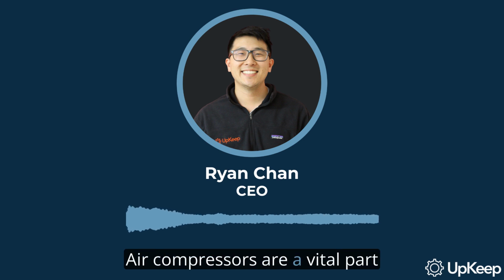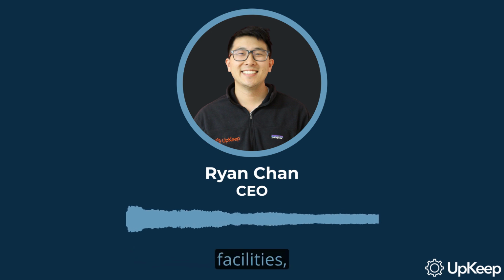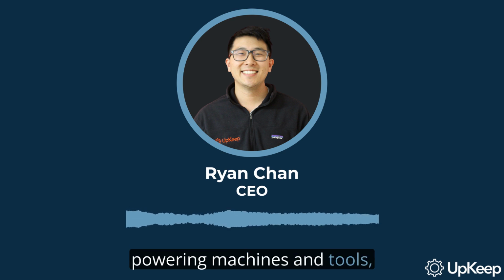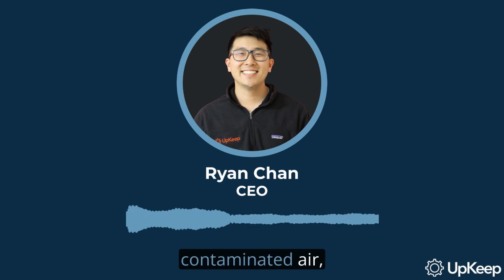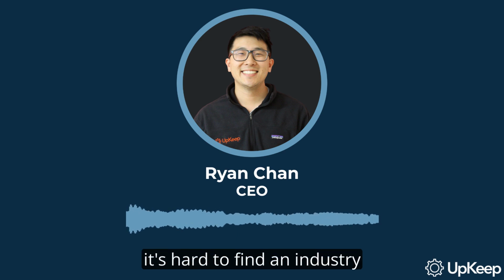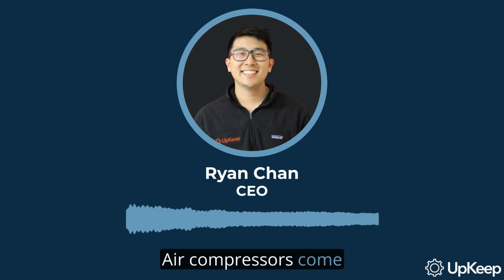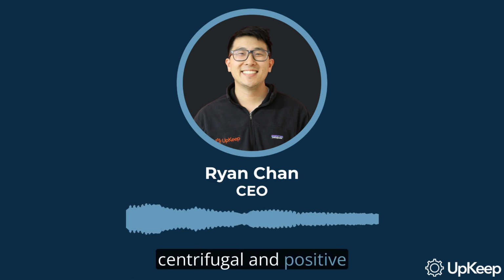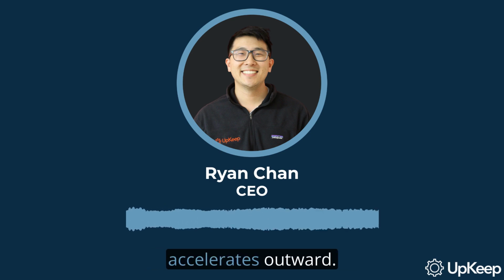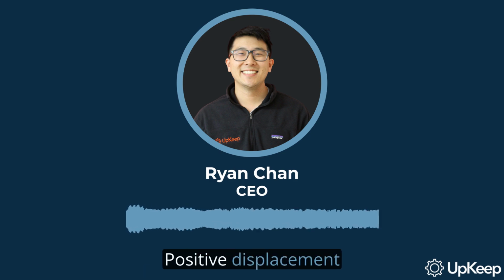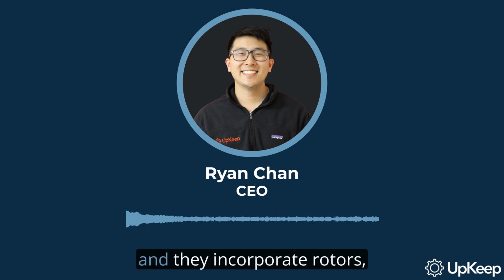Air compressors are a vital part of commercial and industrial facilities, powering machines and tools, exchanging clean air for contaminated air, and running material handling equipment. In fact, it's hard to find an industry that doesn't use air compressors in some capacity. Air compressors come in two main types, centrifugal and positive displacement. In a centrifugal compressor, gas enters the center and accelerates outward. Positive displacement compressors, on the other hand, are either reciprocating or rotary screw, and they incorporate rotors, pistons, or cylinders.